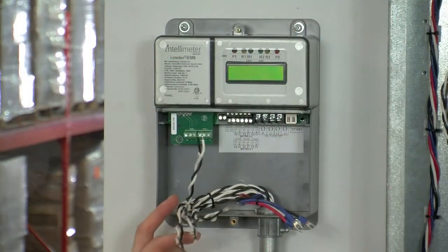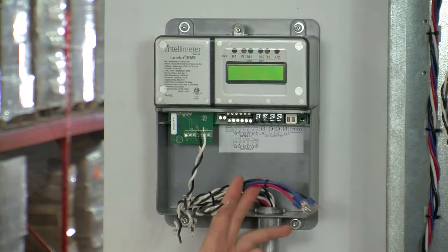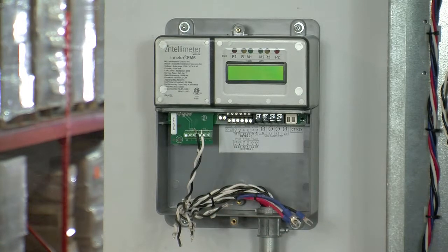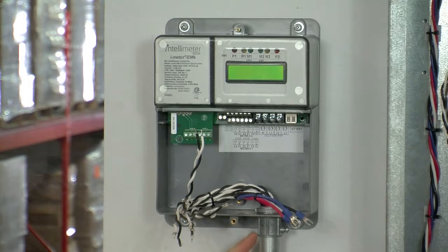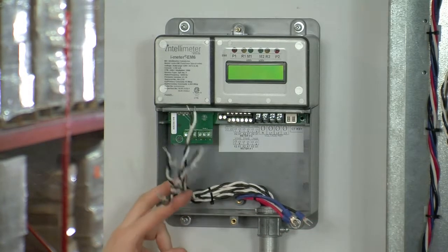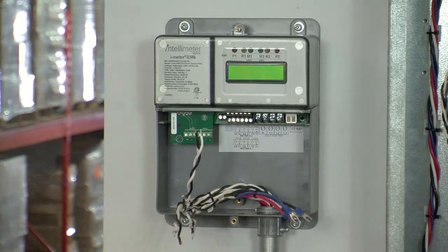As you can see, we now have our CT leads and reference voltage wires pulled through the enclosure. For the sake of this demonstration video, we have pulled them through the 1 conduit. Personally, I would suggest adding a second piece so that you can keep your CT leads and reference voltage wires separate, but for now we're just using the 1.